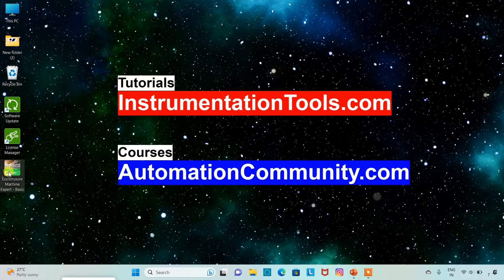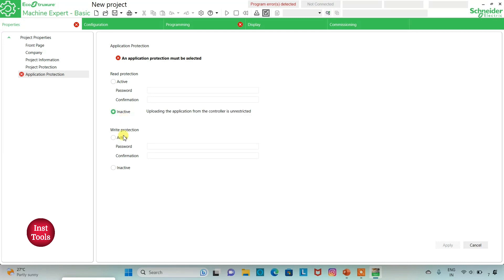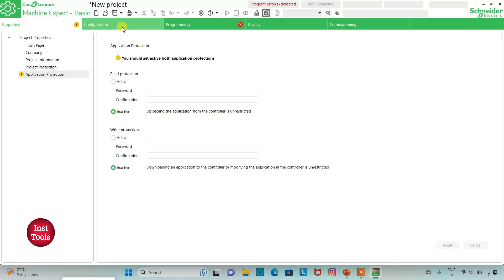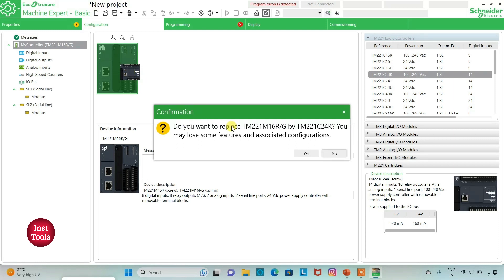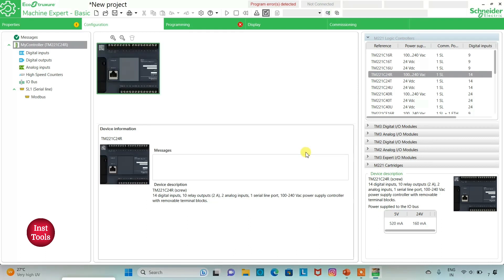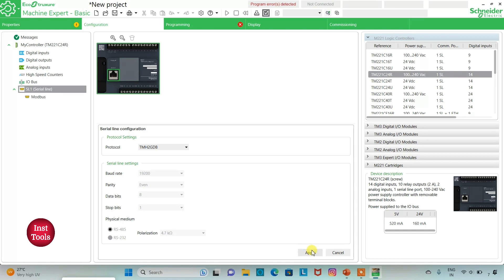I will open EcoStruxure Machine Expert. I will keep read protection as inactive and write protection as inactive, then click apply. I will go to the configuration tab and select TM221C24R from the list of logic controllers, drag it in, and click yes to replace. Then I will go to serial line and select the protocol as TMH2GDB and click apply.